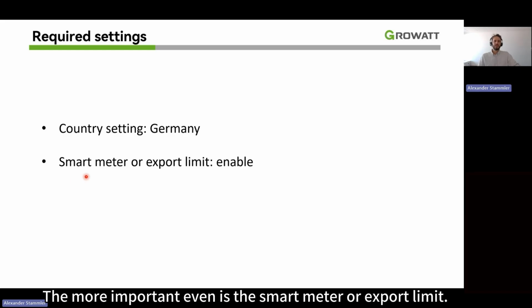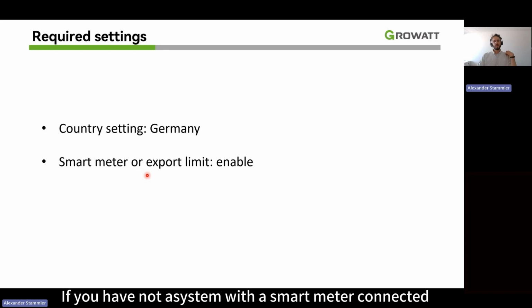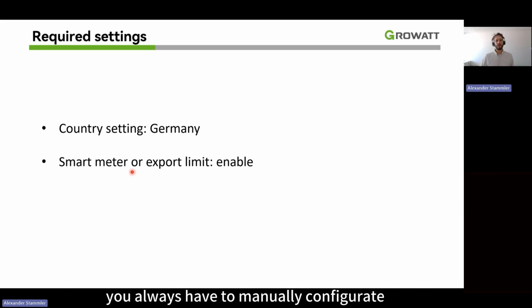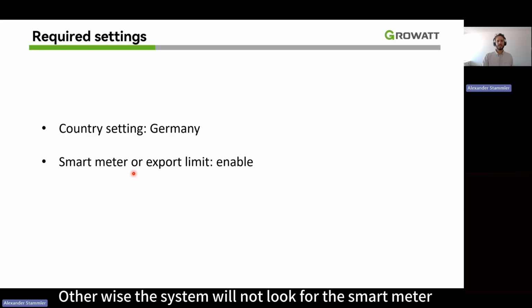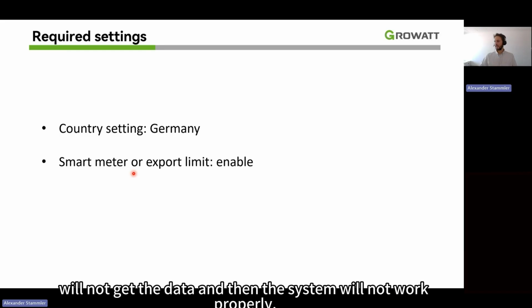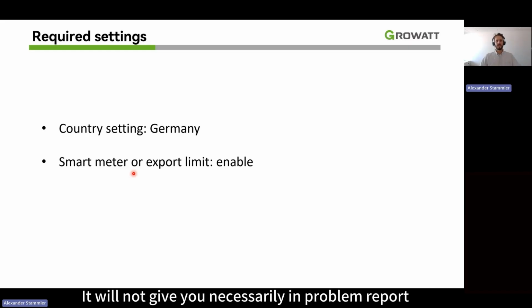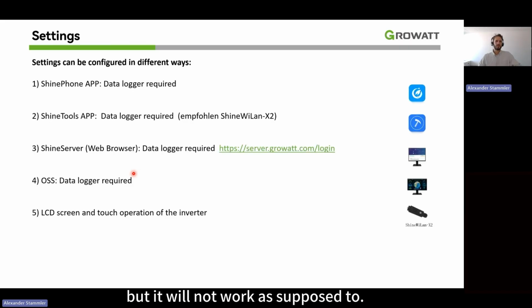The even more important one is the smart meter or export limit. As soon as you have a battery, you need a smart meter. You always have to manually configure either smart meter or export limit. Otherwise, the system will not look for the smart meter, will not get the data, and then the system will not work properly. It will not necessarily give you a problem report, but it will not work as supposed to.